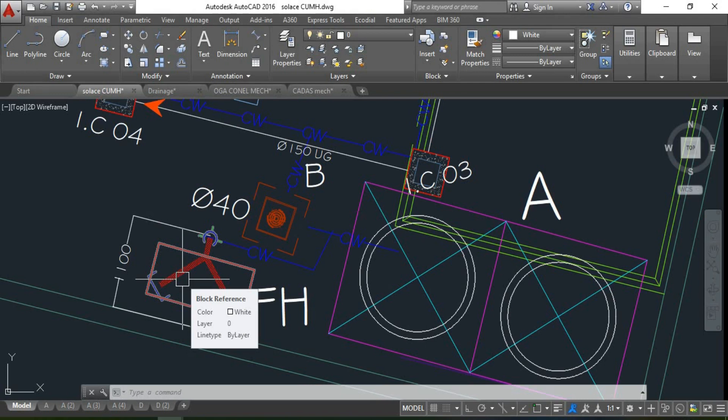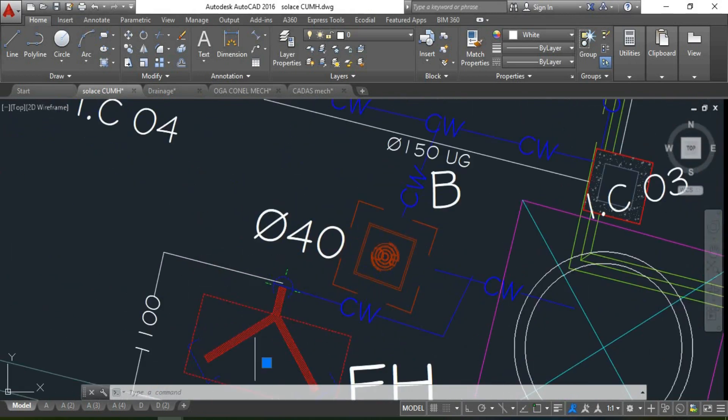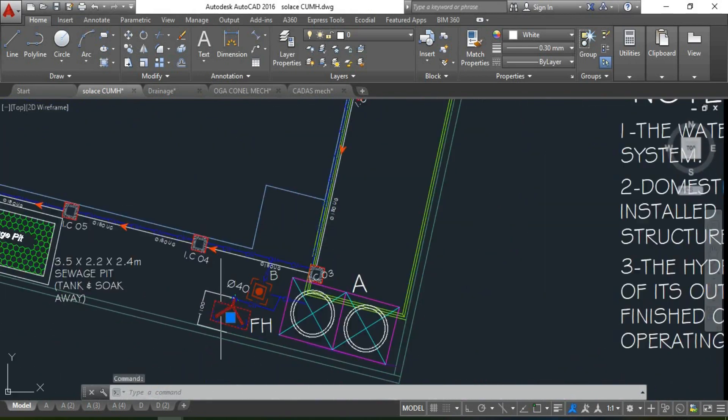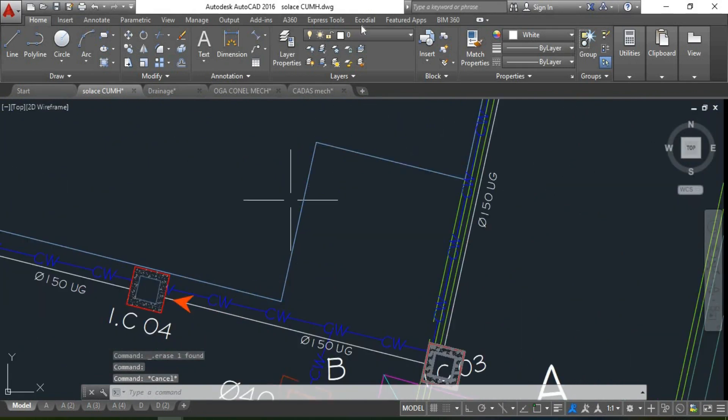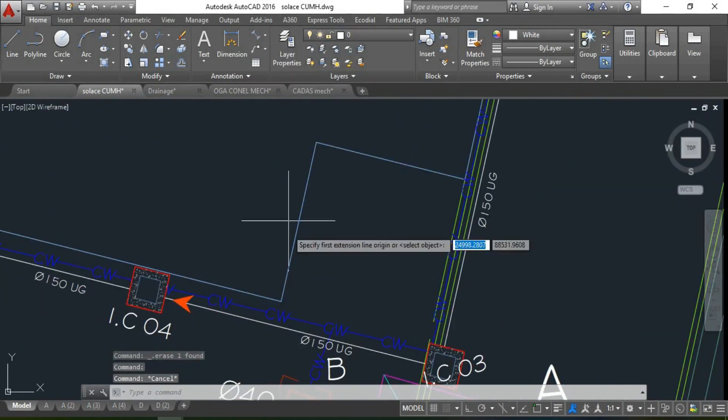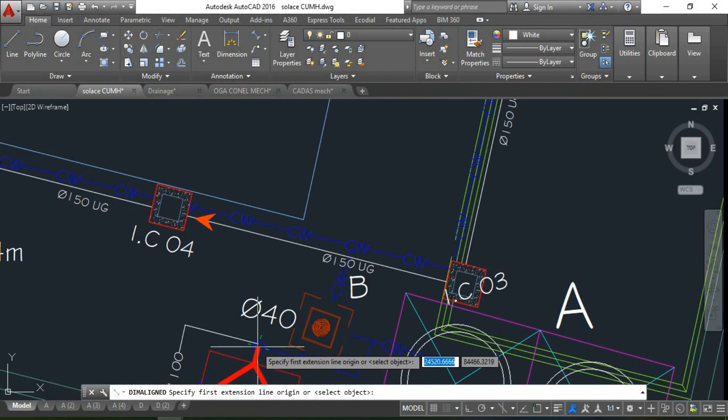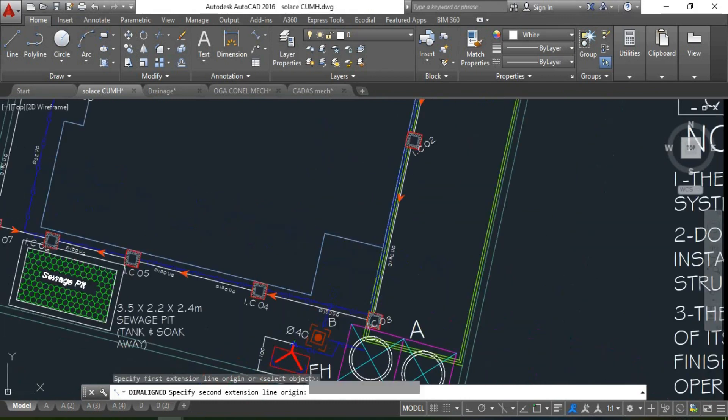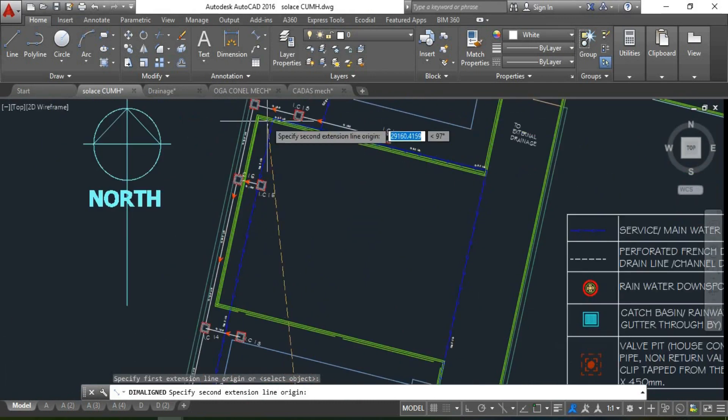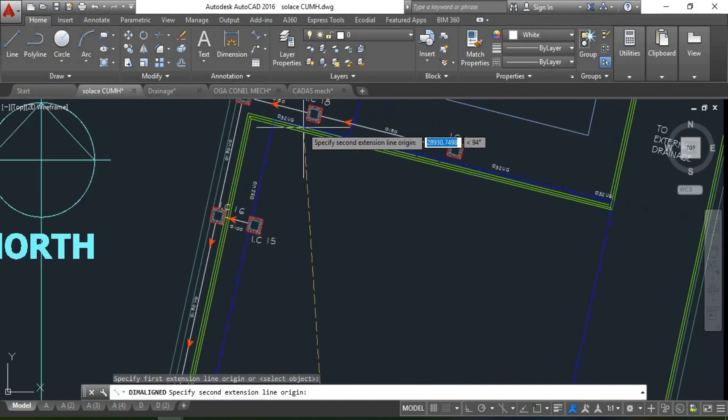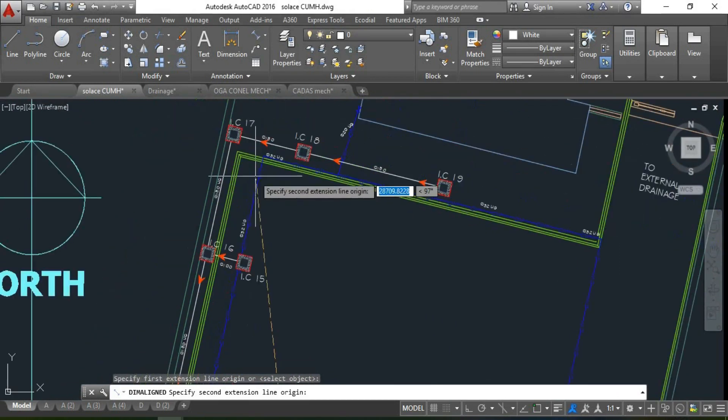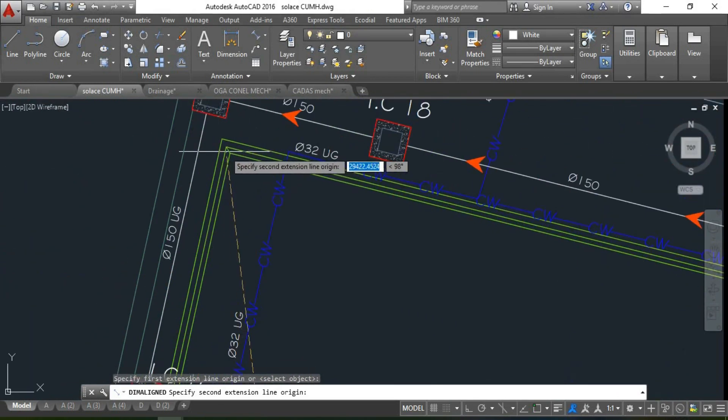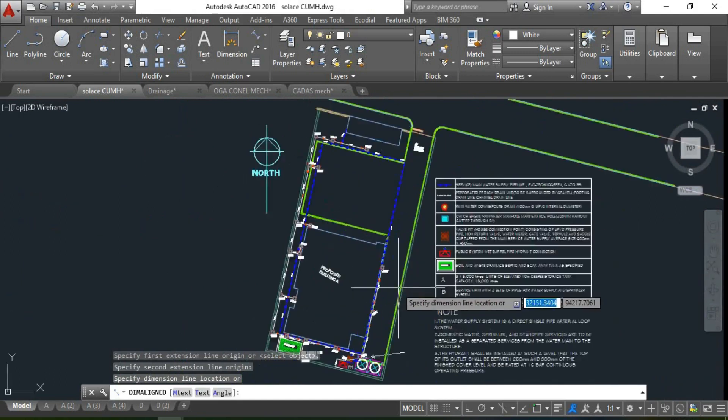One of the basic considerations of an MEP engineer is to ensure that every building part is within 45 meter range of the hydrant. By placing my hydrant here, let's take the dimension. From my hydrant here, this is where the building ends. By taking the dimension, you have almost 30 meter, that means this design conforms with it.